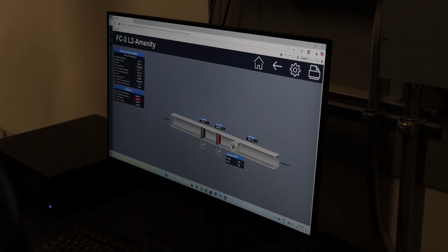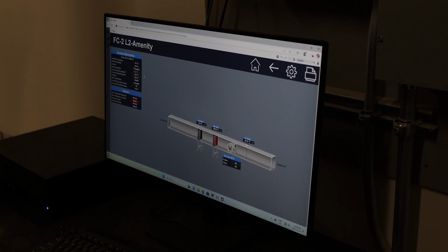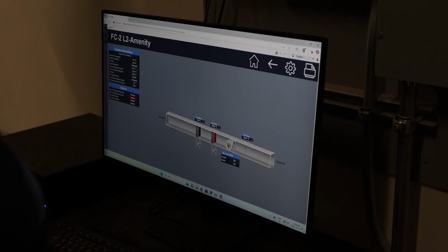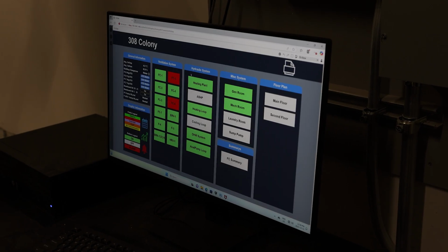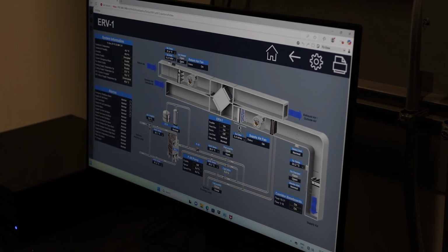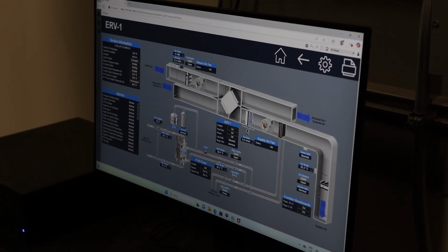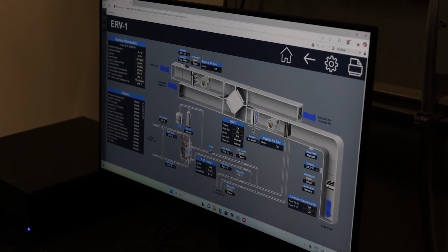Once the construction is finished, the door stays closed, the room temperature will be good. Yeah, that's for the fan coil unit. And this is for HRV, ERV, the big ERV in the penthouse we looked at. So it has an outside damper, and it also has return air damper, return air temperature, return air humidity, and we have a fan status.